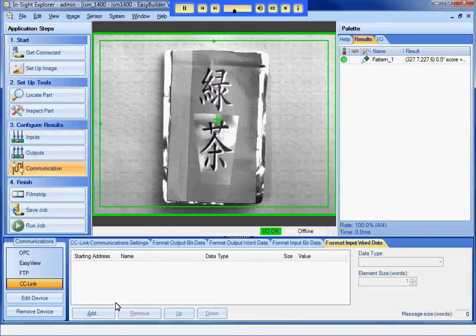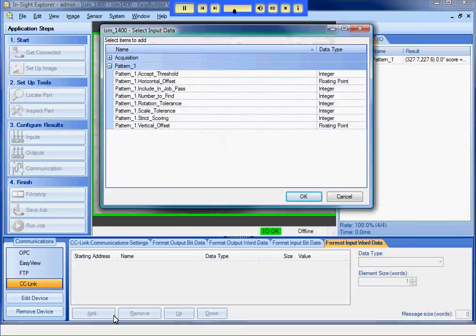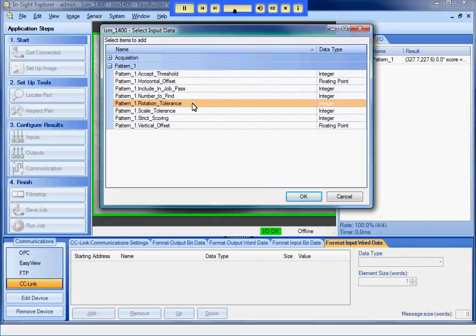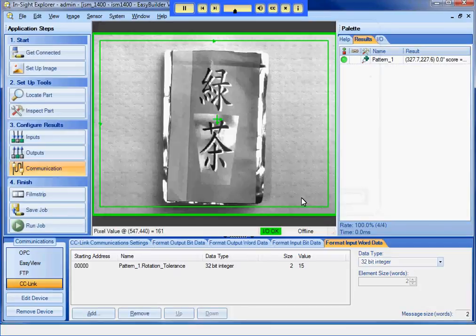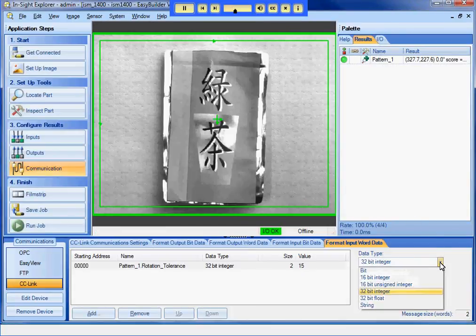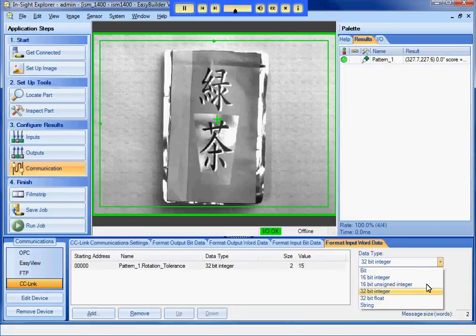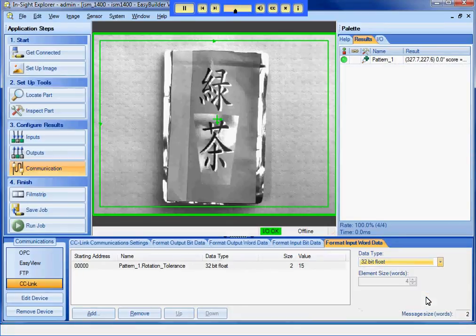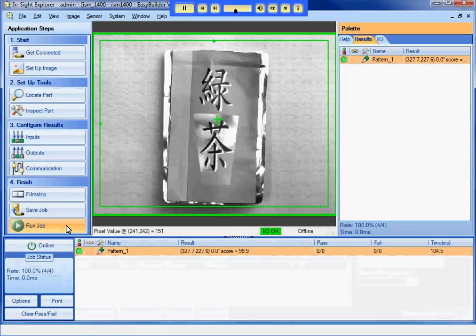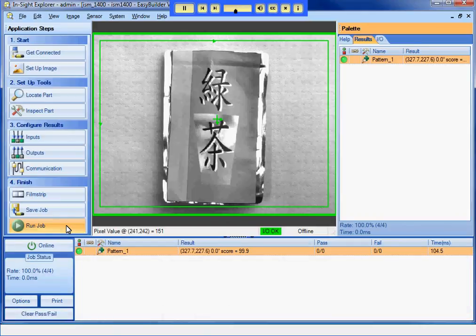In the Format Input Word Data tab, I can add values to read from the PLC. I will choose Rotation Tolerance so my PLC can set the amount of rotation that PATMAX will use to find the part. I can leave the data type as a 32-bit integer, or I can choose a different type. I will choose a 32-bit float. I will put Insight Online and switch to GX Developer to set up the PLC.